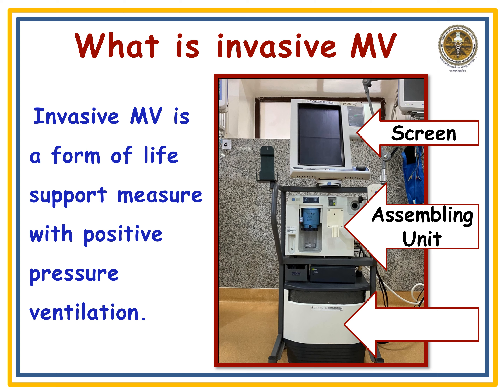At the back of the ventilator there are two tubings: one for medical air and another for the oxygen hose pipe. You connect those tubings to the medical air source and the oxygen source respectively. There is also a power cord for power supply. Connect all these things before starting your ventilator.